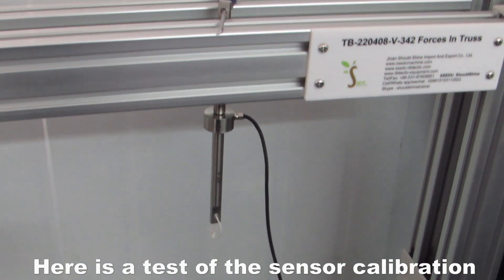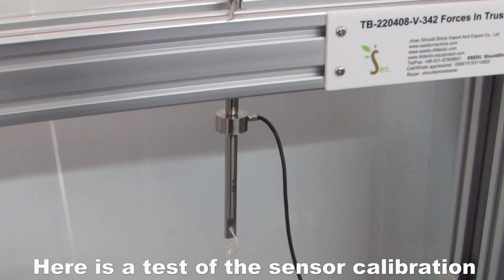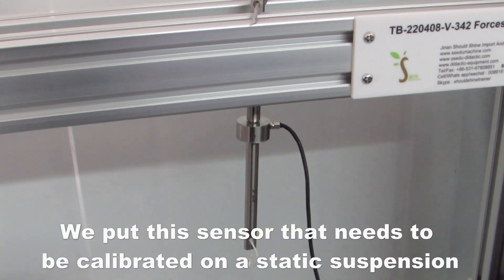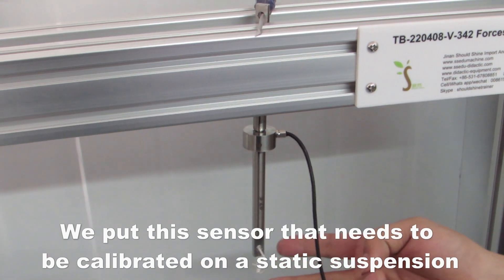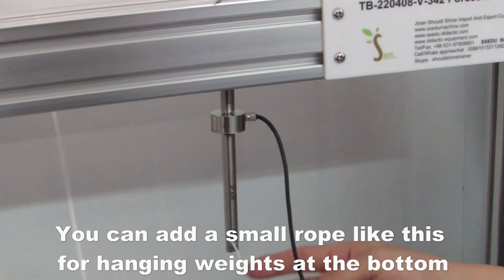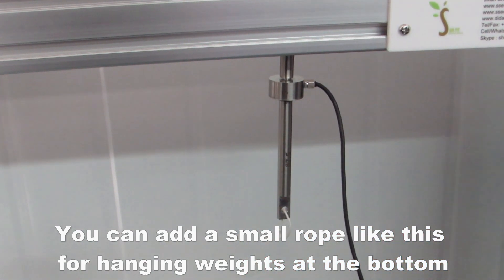Here is a test of the sensor calibration. To calibrate, the first step is to put this sensor that needs to be calibrated on a static suspension. You can add a small rope like this for hanging weights at the bottom.